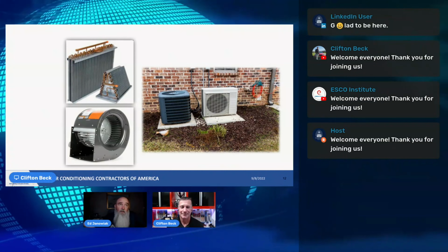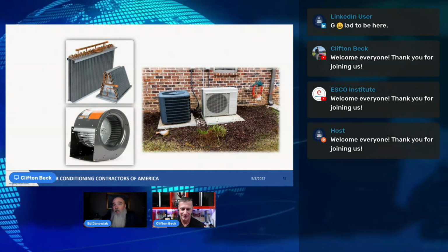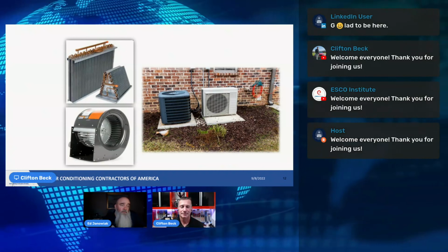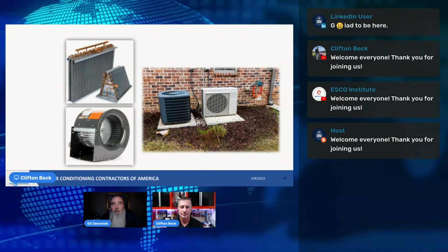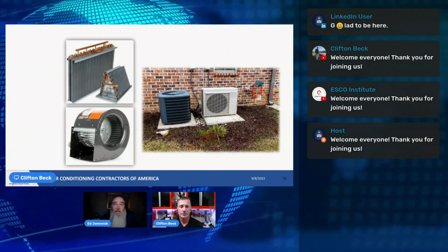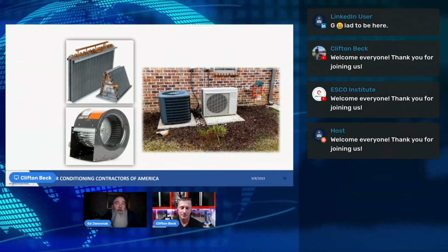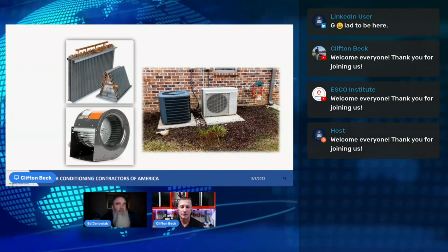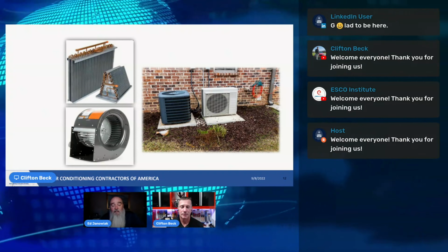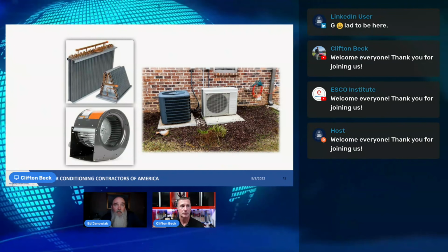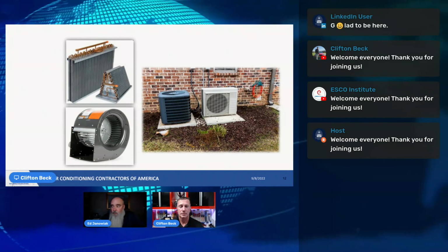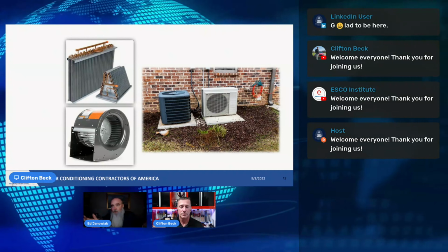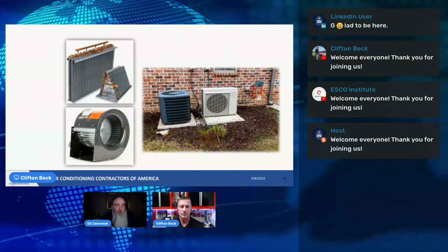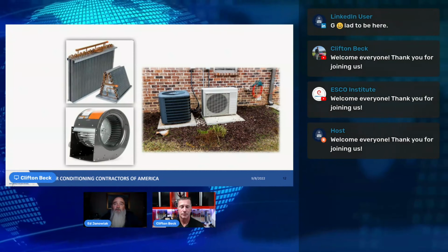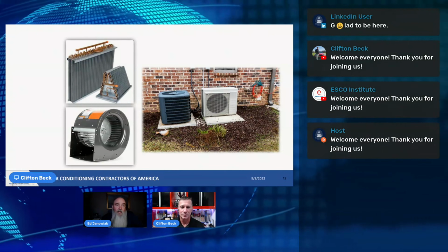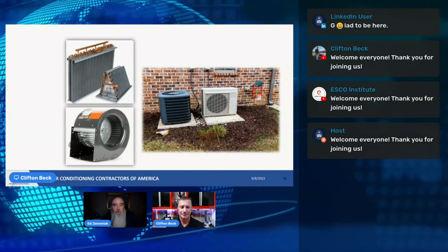When airflow is lower, they'll dehumidify better. When airflow is higher, they'll give more sensible and total BTUs. Sometimes we have control over that, sometimes we don't. The biggest problem I see in today's market is people automatically assuming a 1 ton or 2 ton mini split technology piece of equipment is going to do a fabulous job conditioning that space. And it's not the equipment's fault.